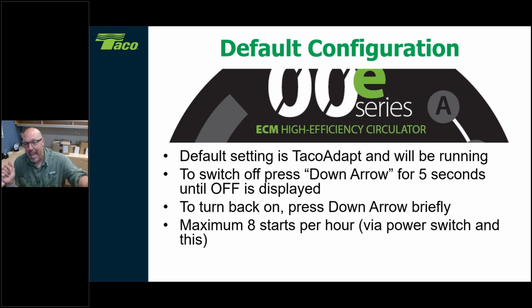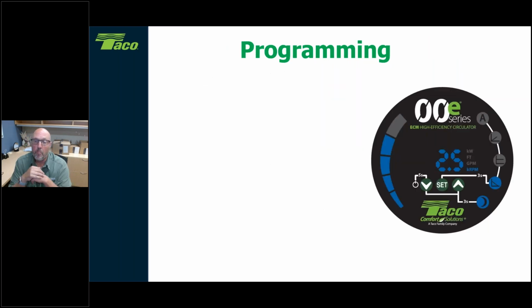When I say it can be, I mean the smaller 120 volt versions can physically be connected to it, and it would turn on and off, but the circulator does not like that. So we are not going to hook these up to a switching relay. We do not want to do that here, because we don't want to see more than 8 starts an hour.